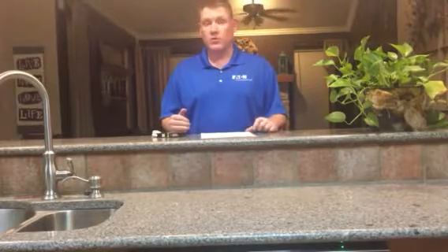That is more complex. In its system, it will have what they call sensors, or CTs, current transformers, which monitor the current coming in and through the breaker, and in turn, when it sees an overcurrent situation or instantaneous or a ground fault, it will trip the breaker instantaneously. That again protects you, us, the population from catastrophic events. It could mean just burning the house down, could mean a short circuit state, could mean electrocution or death.